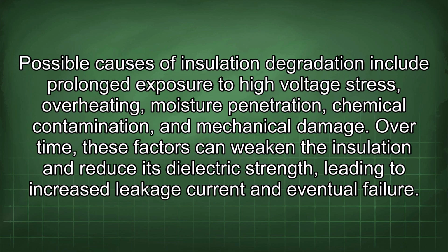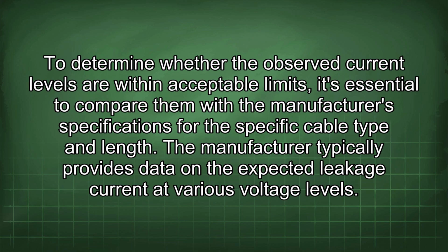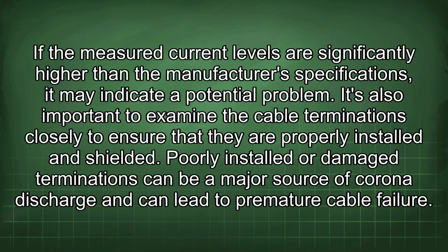Possible causes of insulation degradation include prolonged exposure to high voltage stress, overheating, moisture penetration, chemical contamination, and mechanical damage. Over time, these factors can weaken the insulation and reduce its dielectric strength, leading to increased leakage current and eventual failure. To determine whether the observed current levels are within acceptable limits, it's essential to compare them with the manufacturer's specifications for the specific cable type and length. The manufacturer typically provides data on the expected leakage current at various voltage levels. If the measured current levels are significantly higher than the manufacturer's specifications, it may indicate a potential problem.